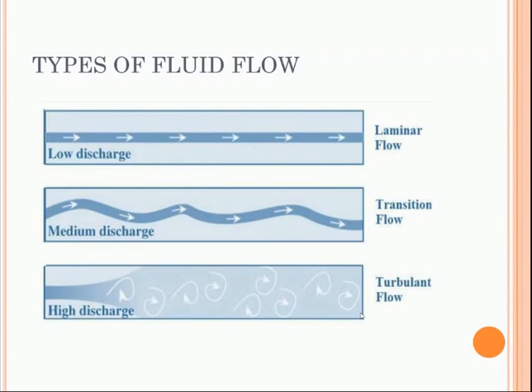How does the type of flow affect friction in pipes? In laminar flow, the friction factor represents the loss of pressure of a fluid in a pipe due to interactions between the fluid and the pipe. It is only a function of the Reynolds number and is independent of the surface roughness of the pipe. In fully turbulent flows, the friction factor depends on both the Reynolds number and the relative roughness of the pipe wall.